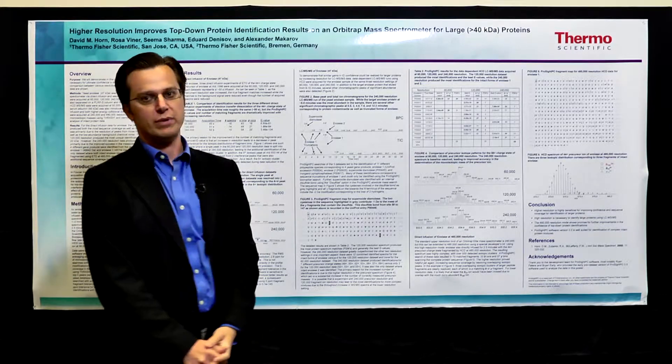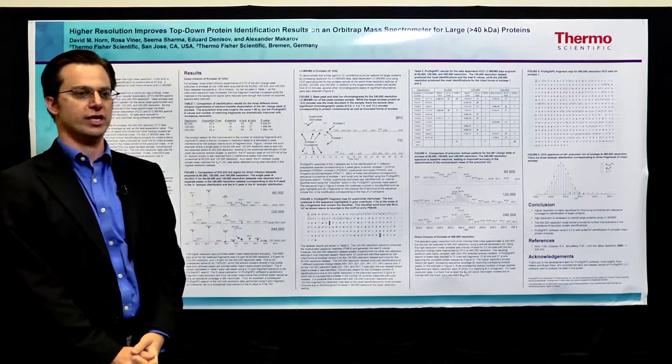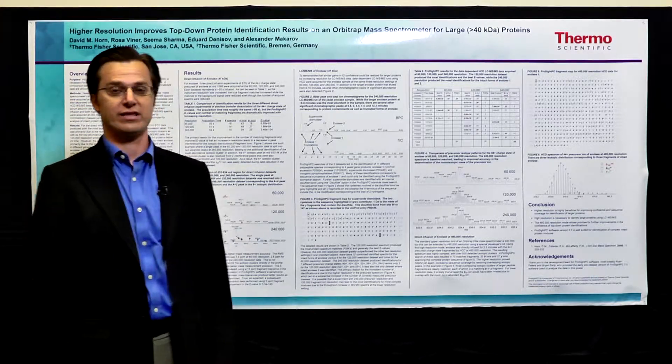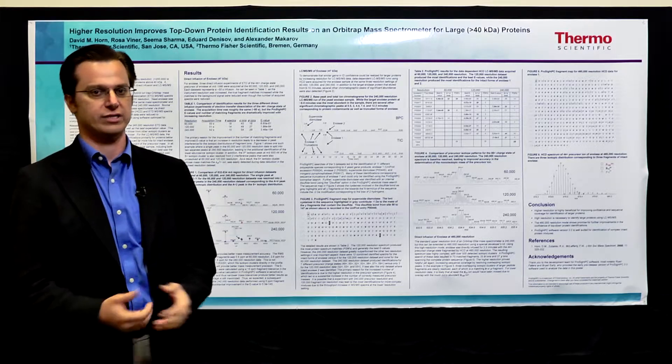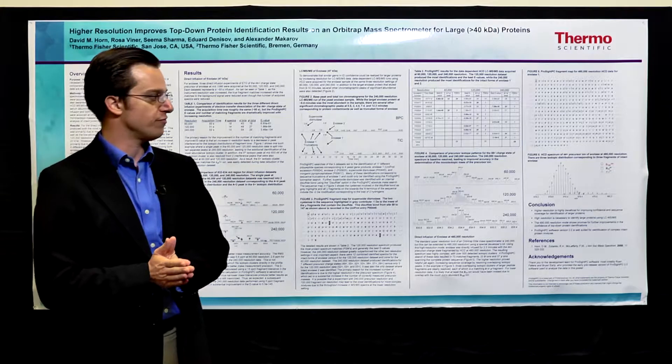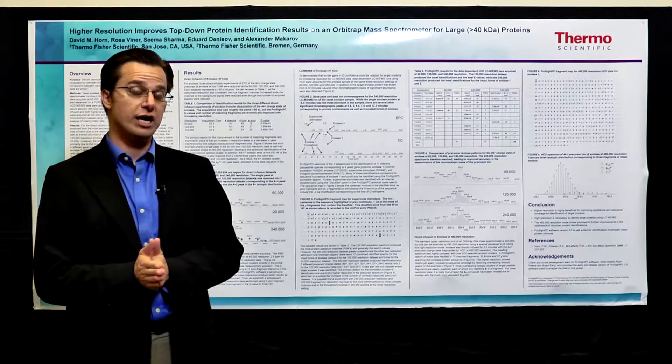Finally, we modified the instrument acquisition software using a special developers kit so we could detect data at 480,000 resolution. This is not something that's available for all users all the time, but we can, in special situations, set the instrument up to do this. So we did a direct infusion run, just like we did at the beginning, at 480,000, and got very high confidence data.